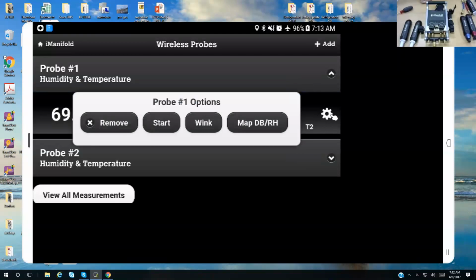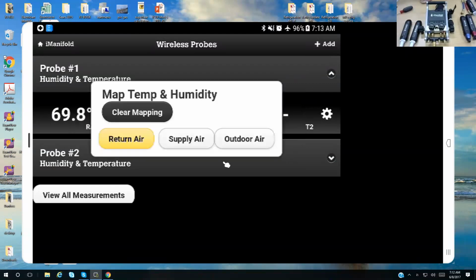We tap on this little gear over here, and it's going to bring up this menu. And we can map it, and it gives us some options. It can be used for outdoor air, the supply air, or the return air. And this can be done at any time. You can change this. If you put the probes in and you realize that, oh, I put this probe in the supply and this one in the return, you can come back to this menu and change it. So I'm going to change this one over to the supply air.